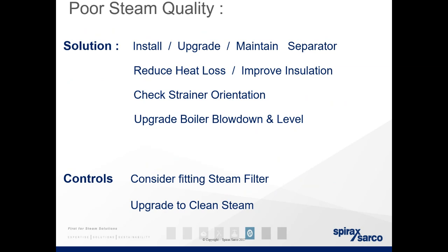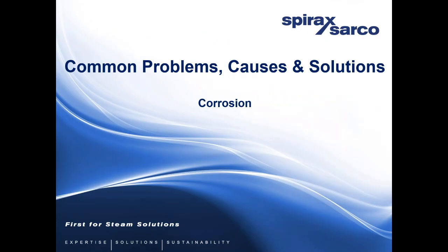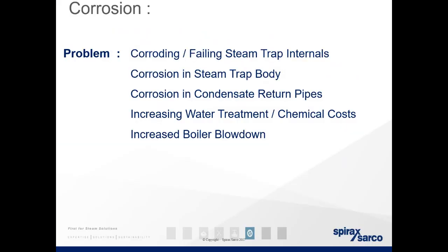Controls, so fitting steam filters where you need cleaner steam, an upgrade to clean steam, with a change of pipe works and so on. The corrosion, so where do we see corrosion? What does it affect? Corroding or failing steam traps and internals. So if you see traps failing open from corrosion, from damage, from water hammer, you're going to see losses. Corrosion in steam trap bodies: most are SG iron or cast iron, which is a little bit more open to carbonic acid. So bodies will see pinholes, pin leaks, slowly corrode away, again giving you losses. Corrosion in condensate return pipes: many of you will see pinholes in joints and bends where you have condensate running, and that will give you a loss.